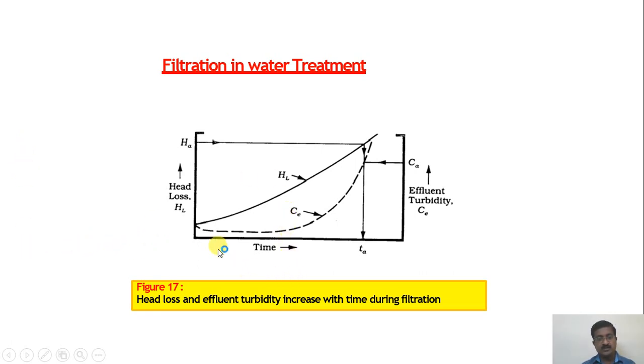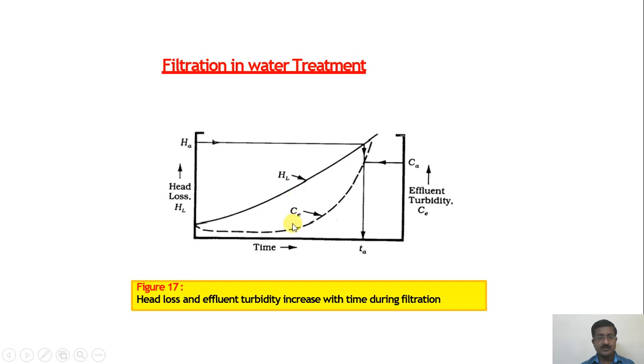A graph of time versus head loss in the filter shows how effluent turbidity also increases with time during filtration. As time passes, turbidity goes on increasing and head loss also goes on increasing. It is necessary to keep close watch on this trend to determine when to carry out backwashing. Different scientists have given formulations to calculate this head loss, which will be covered in subsequent lectures.